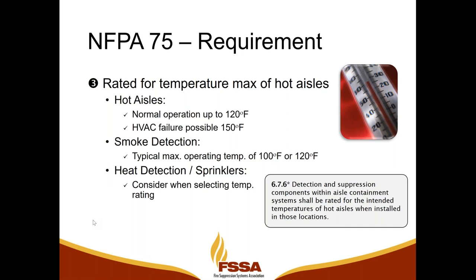And then for sprinklers, consider the temperature selection of the sprinklers. So if we can hit 150 degrees, we don't want to have a normal quick response sprinkler rated for 135 degrees inside of our hot aisle. We may cause an accidental sprinkler discharge if we get that hot of a temperature in the hot aisle. So we need to maybe think about going up in our temperature selection for sprinklers.